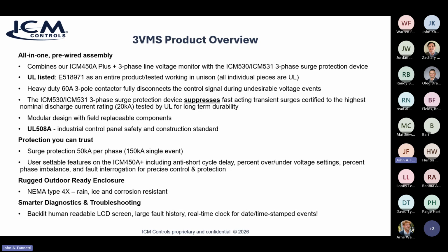User settable features on the 450A Plus, including anti-short cycle delay, over and under voltage settings, percent unbalanced. Although we recommend you stick with the settings that we provide because they're kind of tuned for the device, you can always fine tune it if you need it. It's got a rugged NEMA 4X rated outdoor enclosure and smarter diagnostics and troubleshooting within the 450A, like a backlit human readable display, larger fault history, real-time clock for date and timestamp of the events, so you can do logging of events, find out when these events are occurring, so that helps you better troubleshoot.